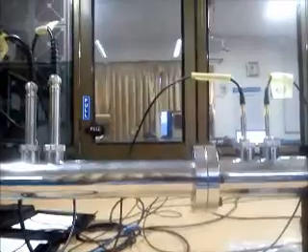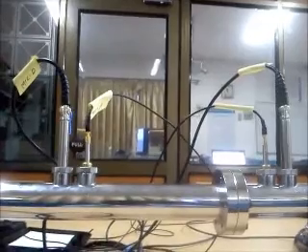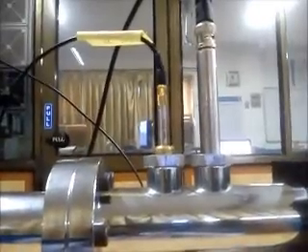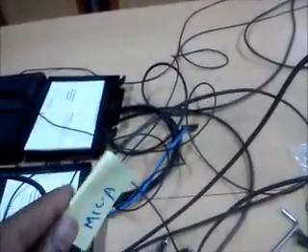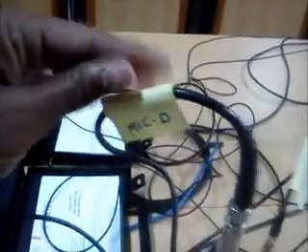So I am showing microphone 1 and 3. I will exchange it and show you. See, now you can see microphones 1 and 3 have been exchanged. Before, there were 1/4 inch on 1 and 2, and 3 and 4 were half inch. So now it is half inch, 1/4, 1/4, half inch. That is microphone C, microphone B, microphone A and microphone D. So A and C have been exchanged.